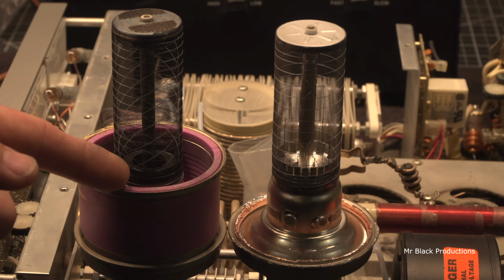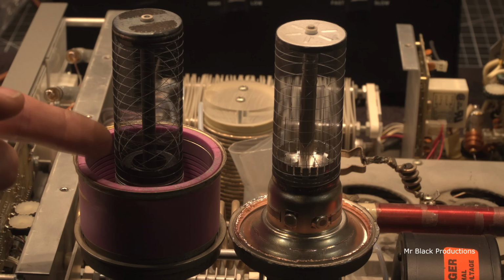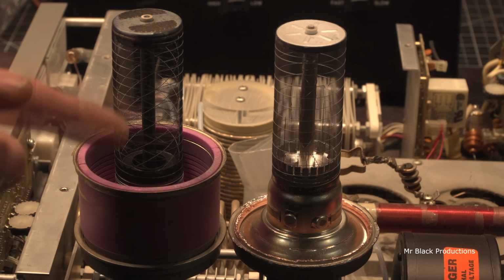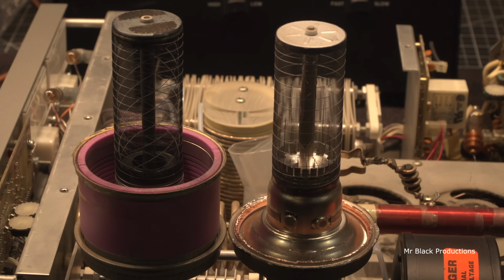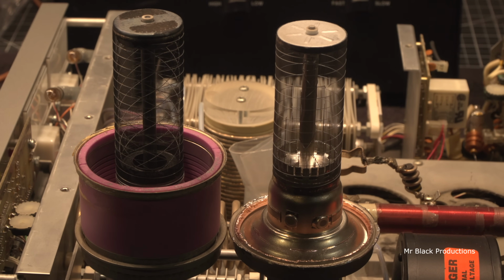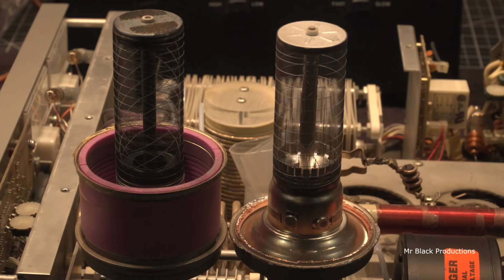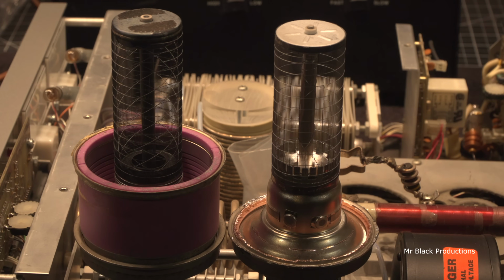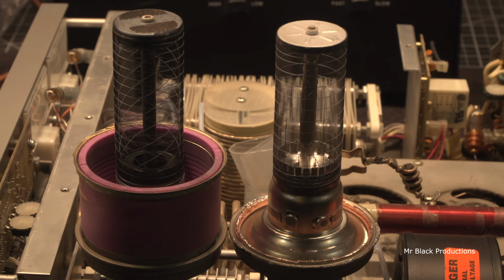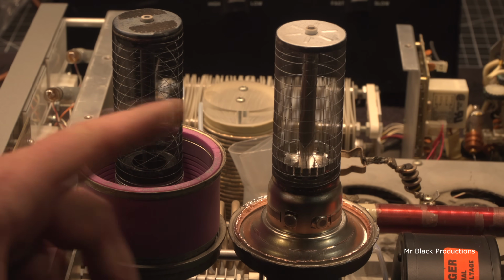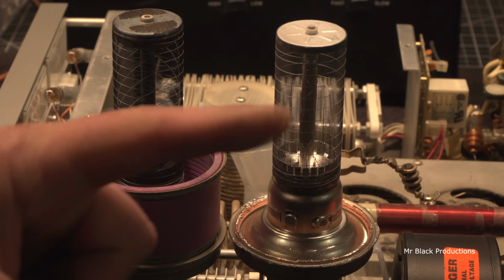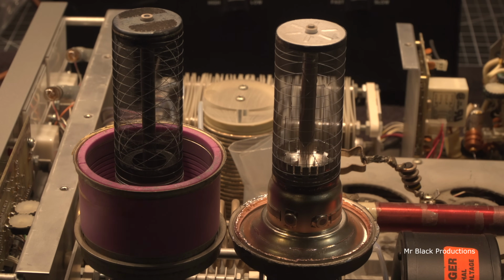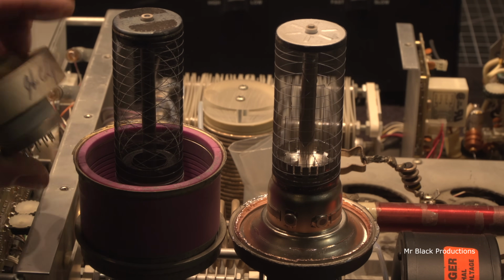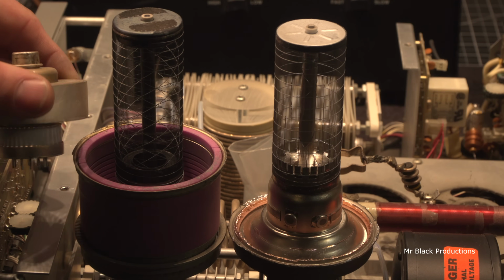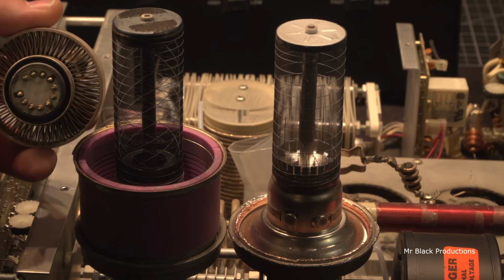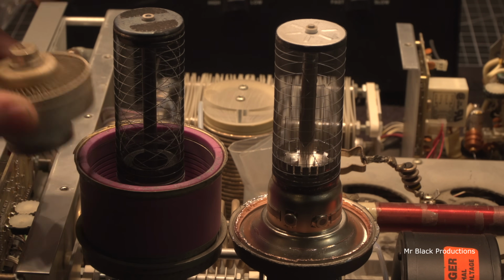This is when oxygen has crept inside of the tube. Slow leak, filament lit. The oxygen started to react with the metal on the inside of the tube here. The tungsten, can't remember the exact name right at this second. And it started to oxidize and disintegrate. It created smoke. This is a filament short, this is a vacuum leak. But I keep these two around so people can have a visual idea of what we're looking at on the inside of the tube. This same structure is inside of this guy, just on a smaller level. Okay, a little bit smaller level, smaller design, smaller.